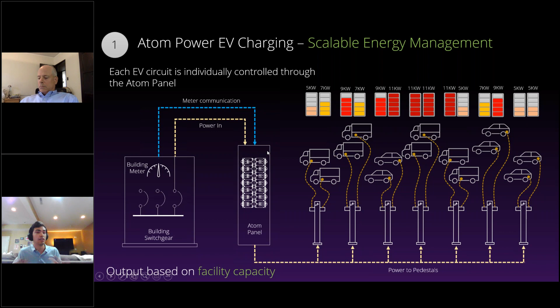We know what everything is pulling, right? But we can't see ahead of the panel for the building unless we put a meter up there with an internet interface, an IP, like an Ethernet port. Then you connect that Ethernet port either directly into our panel or into your local area network, and it now gives us visibility to the entire building. And with that, now that unlocks all of your system capacity by subtracting the actual building load from the maximum capacity. Like, for example, if you had a 500 kilowatt transformer or something feeding your building.